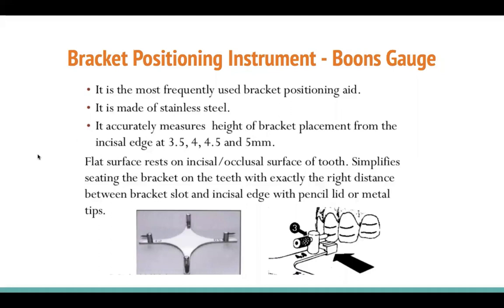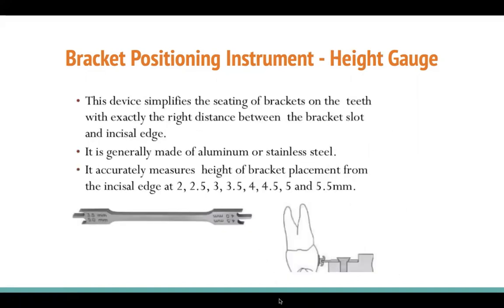The flat surface of the bracket positioning instrument rests on the incisal or occlusal surface of the tooth, simplifying bracket seating with exactly the right distance between the bracket slot and incisal edge. The rod-type device works the same way — use whichever edge corresponds to your desired measurement: 3.5mm, 4mm, 4.5mm, or 5mm from the incisal edge. It is generally made of aluminum or stainless steel and accurately measures the bracket placement height.